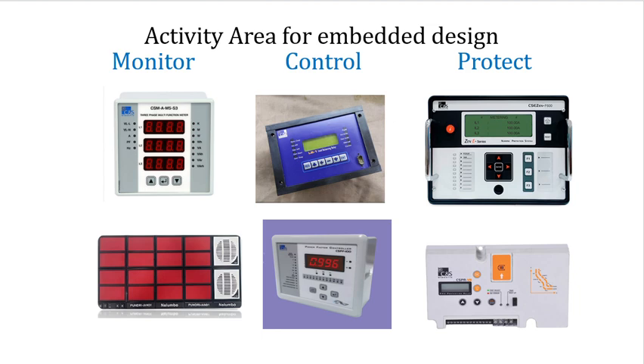For example, when you monitor a switch, even if it has potential free contacts, we first translate it to logic 0 or logic 1 voltage level. If we measure current, we first pass it through a resistor and convert it to voltage. If we measure temperature, it is also converted into voltage first by what is known as the transducer. So the transducer converts temperature into voltage. This is true with every parameter. So our first priority is to see how to convert various parameters into voltage.